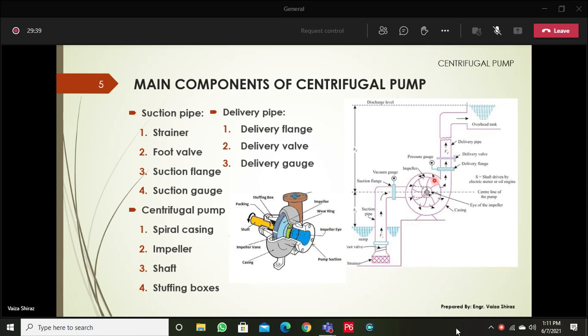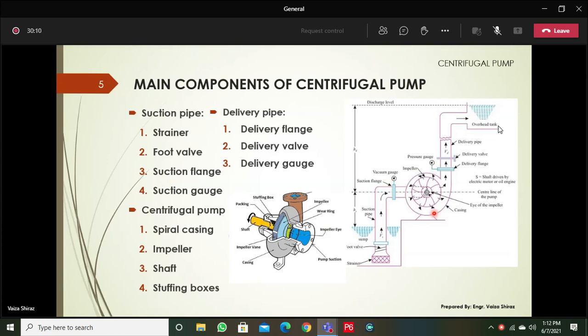This casing is a spiral casing. The flow area is not uniform along the flow direction — it varies. You can increase or decrease the flow area depending on the requirement. In this case, to increase pressure, the spiral casing increases the flow area, which reduces velocity and increases pressure in the water. Finally, the water leaves the casing with high pressure and is delivered out from the delivery pipe.